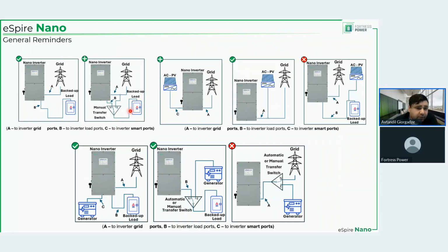So normally, obviously, there will be grid coming in, flowing through the inverter, coming out on the normal port, and going to the backed up load. But if something happened to the inverter or you need to do some kind of maintenance, you can change the position of the arm of the transfer switch or bypass switch. And that way, the inverter, yes, is receiving AC power unless you turned off the AC disconnect upstream of it, but it cannot deliver any power to the load. There can be no conflicting frequencies on the load side because there is no continuity between the inverter load output or backup output and the backed up load.